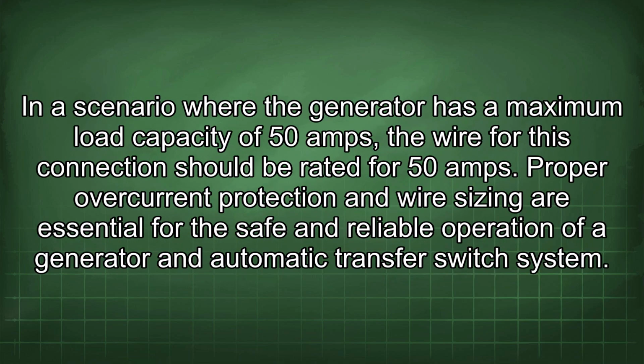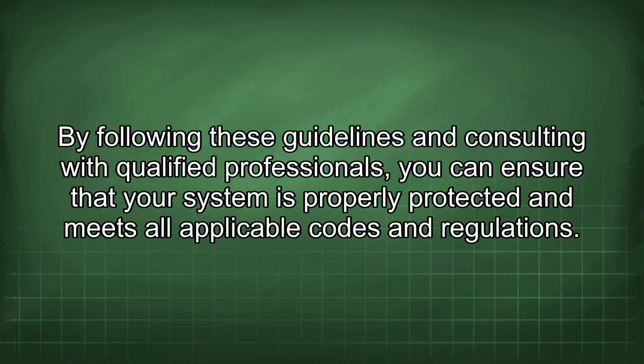In a scenario where the generator has a maximum load capacity of 50 amps, the wire for this connection should be rated for 50 amps. Proper overcurrent protection and wire sizing are essential for the safe and reliable operation of a generator and automatic transfer switch system. By following these guidelines and consulting with qualified professionals, you can ensure that your system is properly protected and meets all applicable codes and regulations.